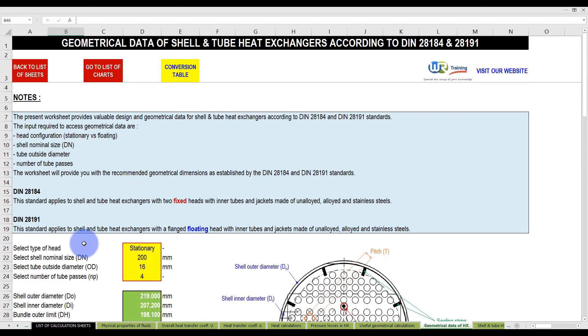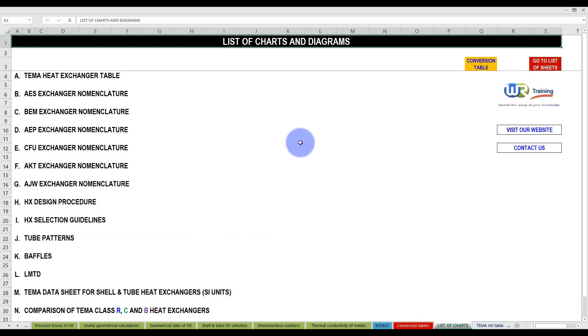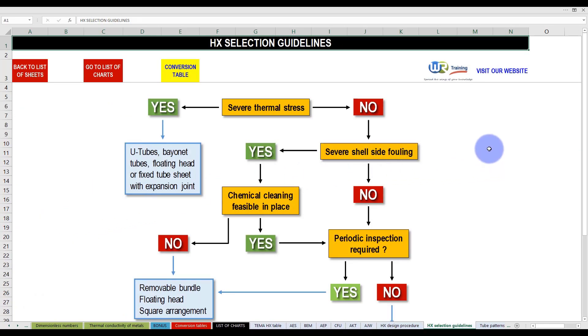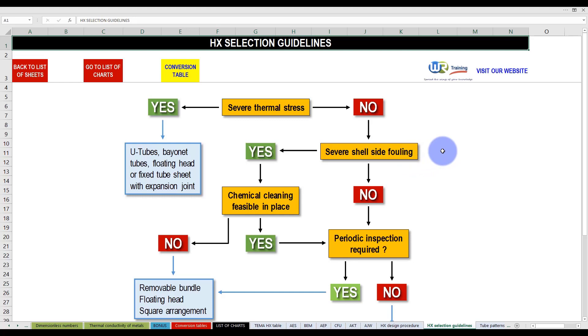Let's now have a closer look at the second section of the workbook that includes charts and diagrams. To do that, we can either go back to the welcome page and select charts and diagrams, or simply click on the button 'go to list of charts.' This will bring us to the chart index. I'm not going to go through each diagram, but will only walk you through one example. Let's suppose we need to design a shell and tube heat exchanger and need guidelines regarding the best configuration for our application. We will click on 'heat exchanger selection guidelines' and then answer the various questions of the chart — such as: will the heat exchanger be exposed to severe thermal stresses? If no, we proceed to the next question: do we expect severe fouling on the shell side? And so on, until we finally determine which configuration is best suited for our application.